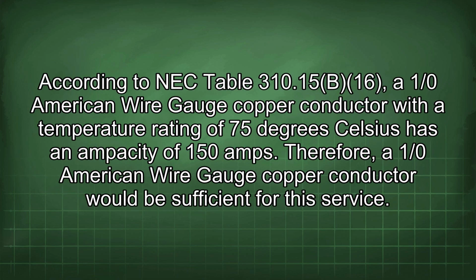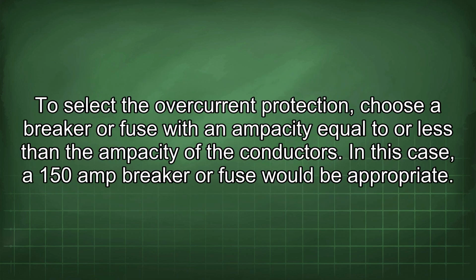According to NEC Table 310.15(B)(16), a 1/0 American wire gauge copper conductor with a temperature rating of 75 degrees Celsius has an ampacity of 150 amps. Therefore, a 1/0 American wire gauge copper conductor would be sufficient for the service. To select the overcurrent protection, choose a breaker or fuse with an ampacity equal to or less than the ampacity of the conductors. In this case, a 150 amp breaker or fuse would be appropriate.